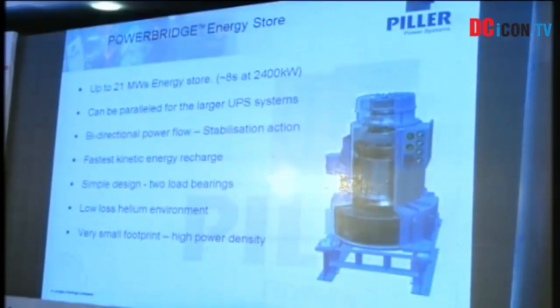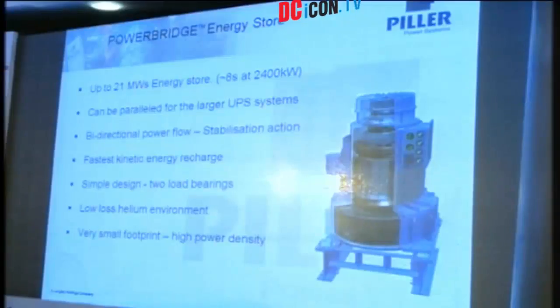Simple design, just two bearings only, right? And a low-loss helium environment. This flywheel rotates continuously, 365 days, 24 hours. So in order to maintain the losses in the machine, you have a helium environment, and this helium environment reduces the losses of the machine. Very small footprint. You can see an equivalent 2000 kilowatt battery system, how big it is compared to a flywheel, which is as small as this, which can be put in a panel and is a vertically standing machine.